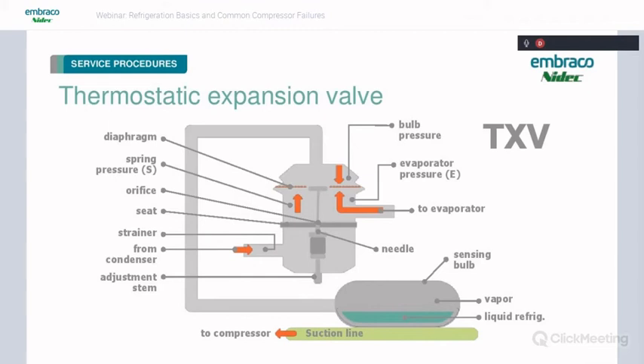And they're very efficient. That's why most of your manufacturers are going to them now, because they're very efficient at giving the correct amount of refrigerant even in low load conditions, whereas a fixed orifice is just going to be feeding the same amount all the time.